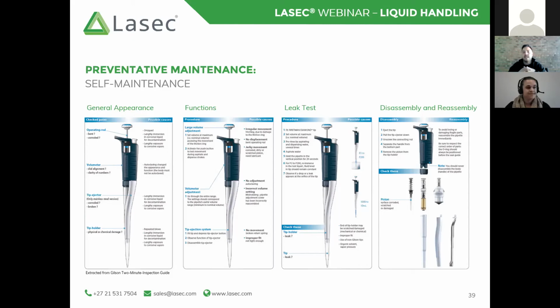So once you've disassembled and reassembled that pipette, it is always advisable to then perform a verification test on that pipette, just to ensure that it is actually aspirating and dispensing the volume that you have set it to.